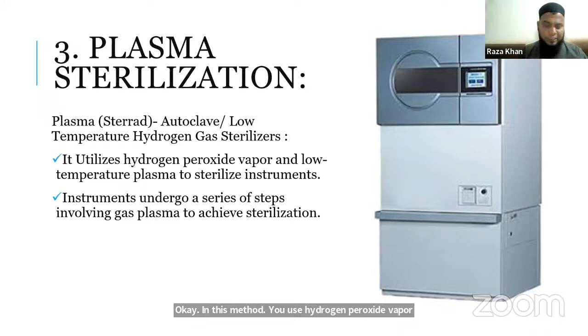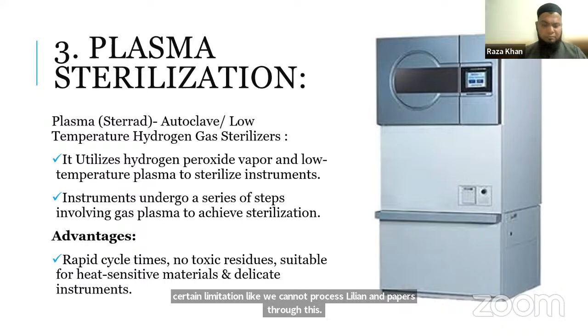The third and the latest method is plasma sterilization, also called low temperature hydrogen gas sterilizer. In this method, we use hydrogen peroxide vapor and low temperature plasma gas to sterilize the instrument. Usually it involves a series of steps to achieve the sterilization. The most common, very good advantage of plasma sterilization is that it is very rapid, very quick. There are no toxic residues in this method. It is very suitable for heat sensitive materials and delicate instruments. It also has certain limitations, like we cannot process linen and papers through this method.